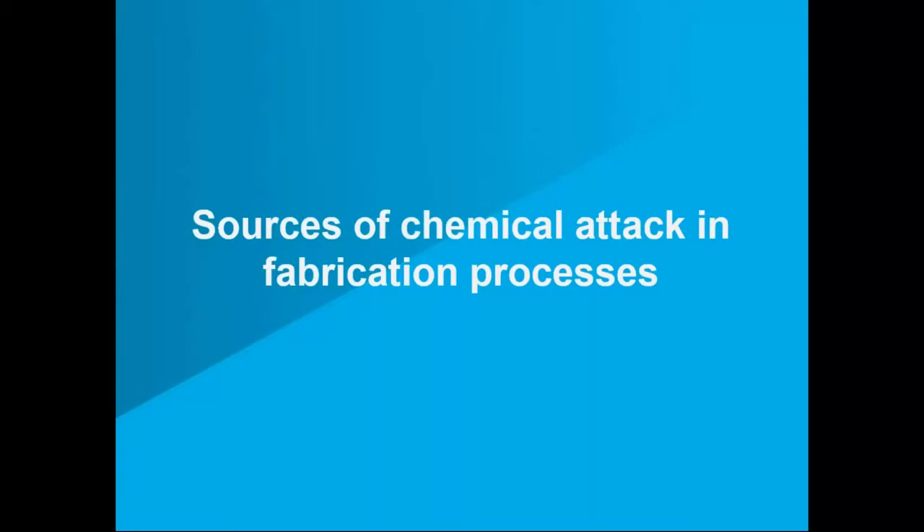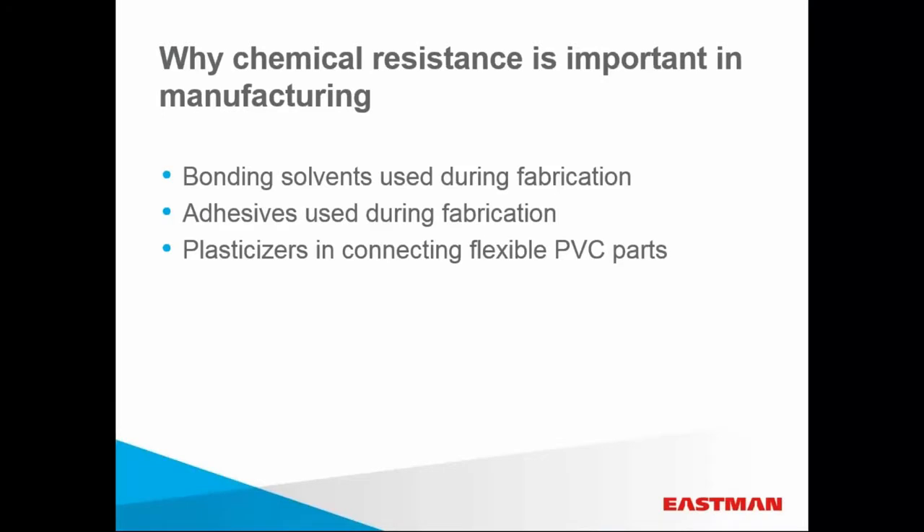Now we'll turn to the sources of chemical attack in the fabrication process. The manufacturing processes themselves can introduce chemical attack. Bonding solvents and adhesives can degrade some legacy polymers, as can the plasticizers commonly used in flexible PVC parts. It's important to examine polymer performance in light of these conditions. In solvent bonding of lures and connectors to tubing, for example, Tritan copolyesters stand up to the solvents without cracking or crazing. And for the bonds formed, the tubing snaps before the bond fails.